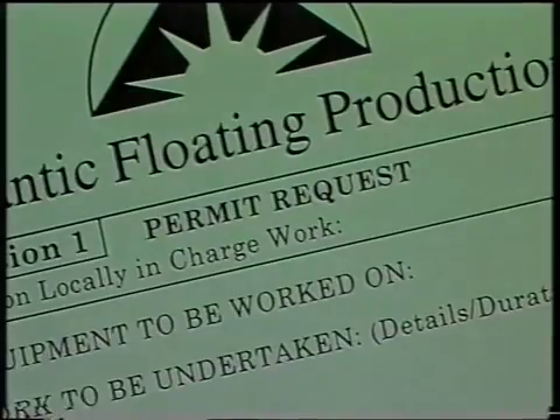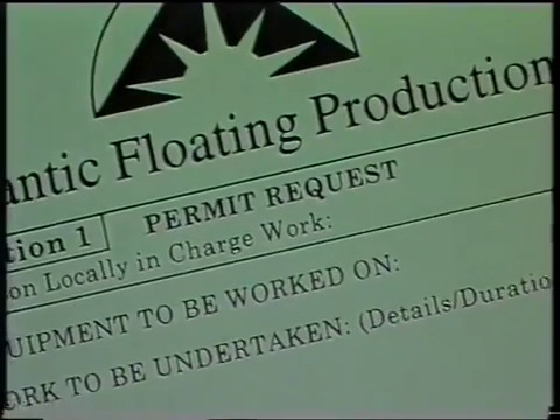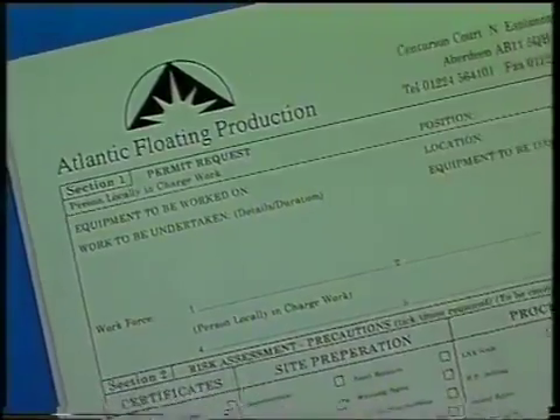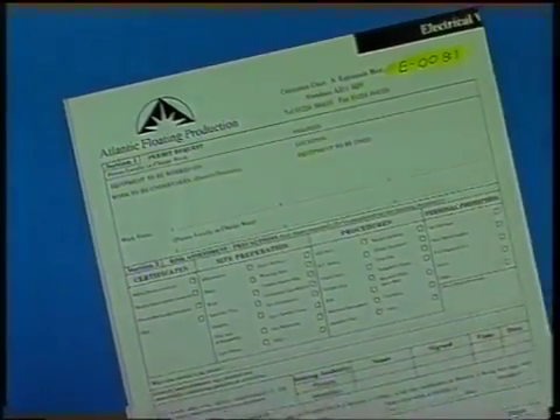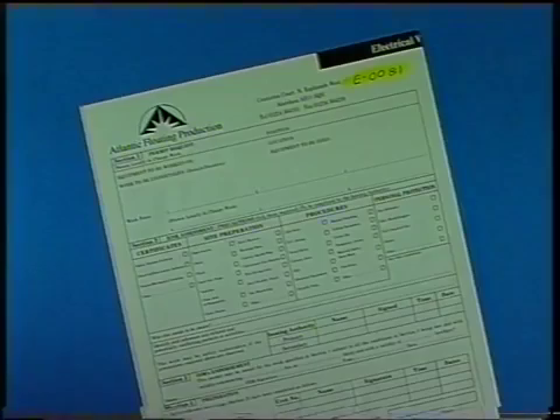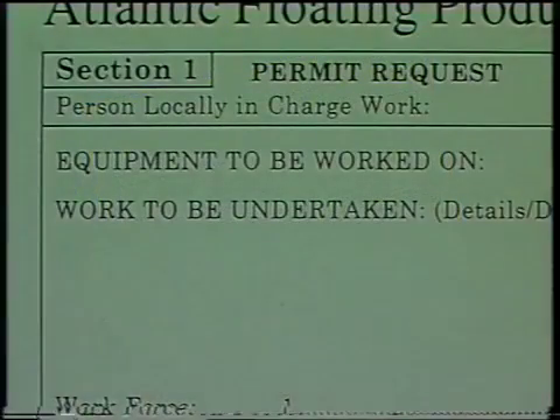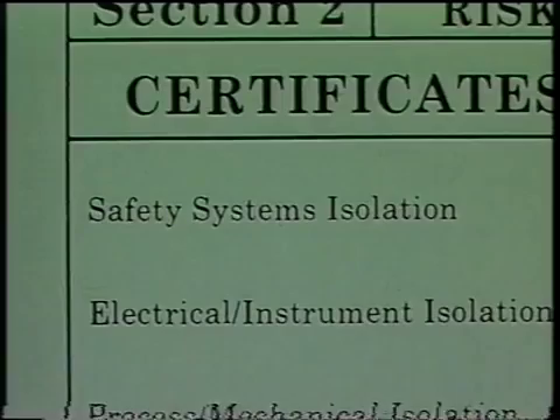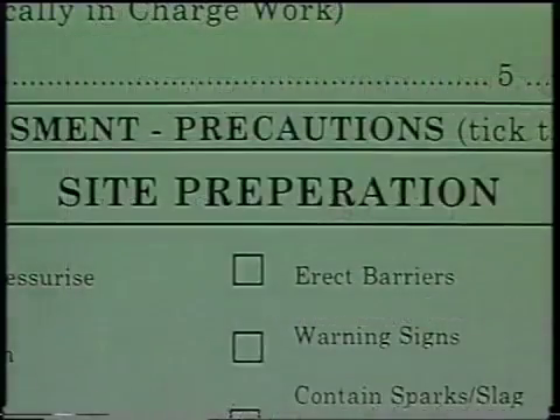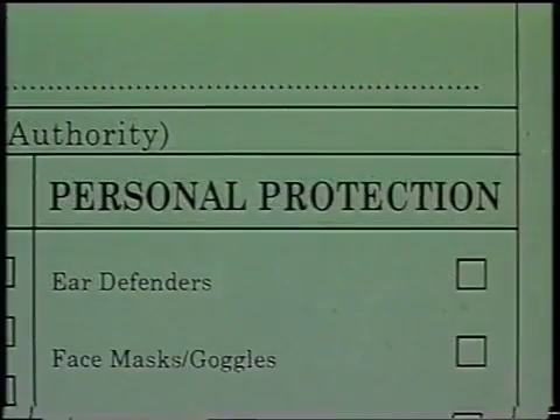High voltage operation necessitates extremely rigorous safety procedures, which you cannot ignore. When investigating any fault or when doing routine maintenance, it is essential that the correct documentation is filled out and countersigned. For instance, good practice would require the Chief Electrotechnical Officer, or CETO, to fill out a permit to work order for a routine insulation test on a high voltage circuit. This would include circuit details and a risk assessment listing isolation points, site preparation and personal protection sections.